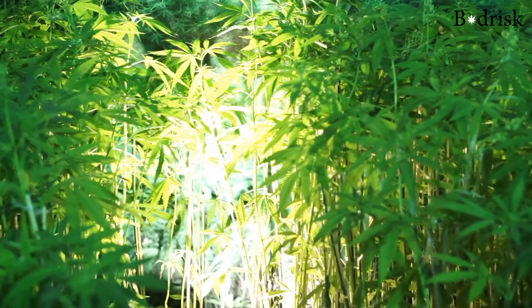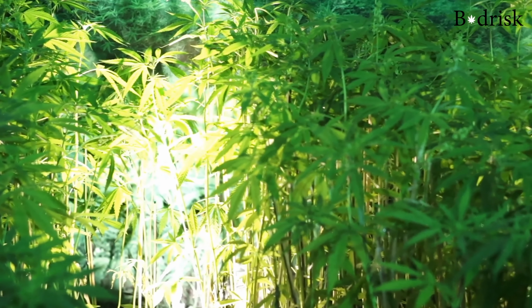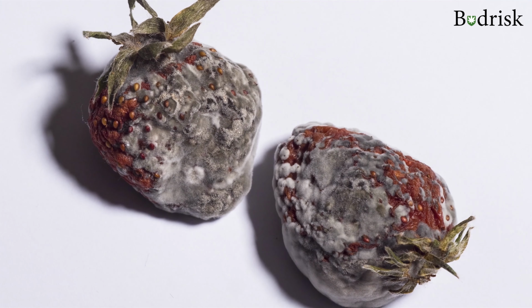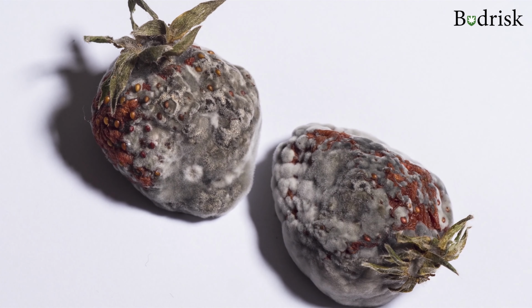Actually, my favorite is we came in behind a contractor who designed a system. They completely messed up the way it was supposed to be designed, just based on a space calculation. They took a heat load based on the size of the room and what they thought the heat lamps were giving off, didn't take into account the total heat load with the heat lamps running 24/7, which they will do frequently, and didn't take into account the humidity. So what ended up happening was they had a mold problem. We went in there, fixed it entirely for them, and then did two other grow rooms for them after that, which worked perfectly since then, with redundancy so they never go down, taking into account how they were going to grow their plants.